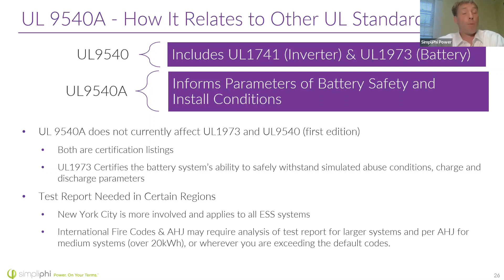New York City has an added requirement that you have off-gassing sensors for any lithium-ion batteries, and we have systems that have been approved with these requirements. So if you're doing an installation in New York, know that we meet the fire codes and have approval there. We can help you with the monitoring systems, which we have packaged as part of our BOSS and our access units for systems for New York.